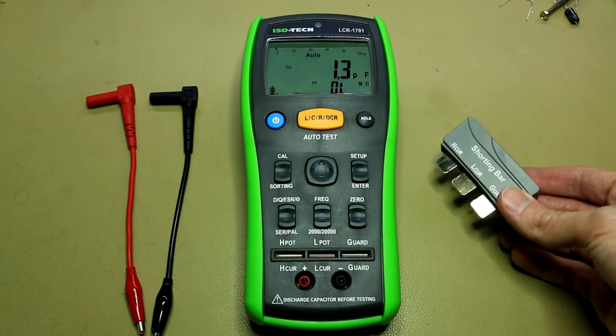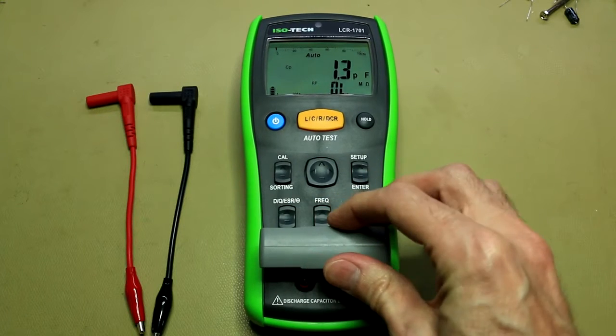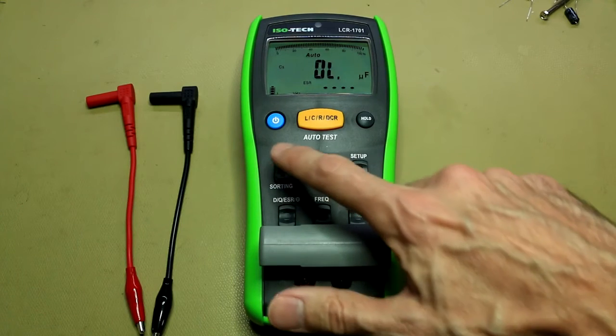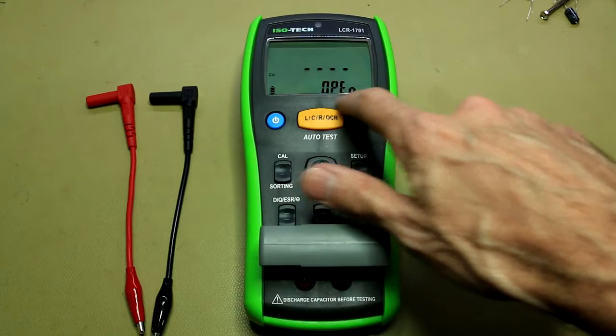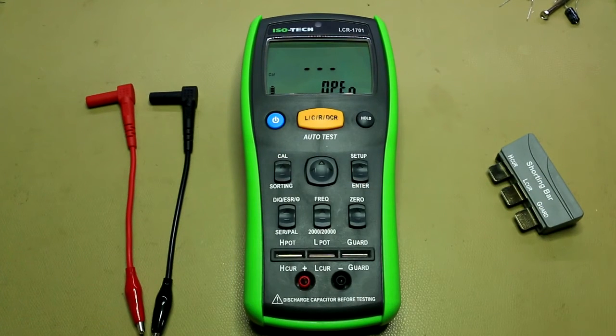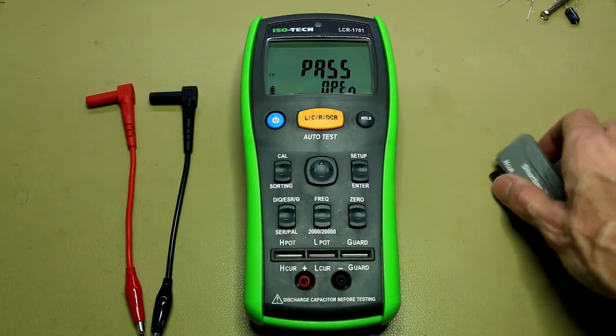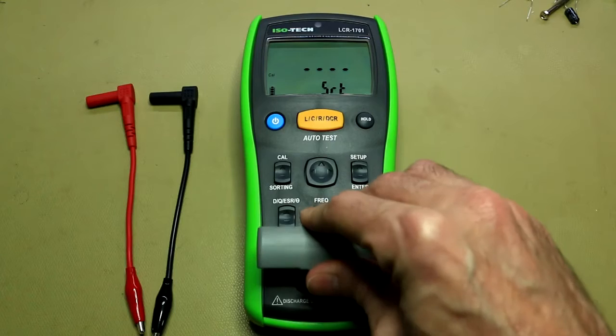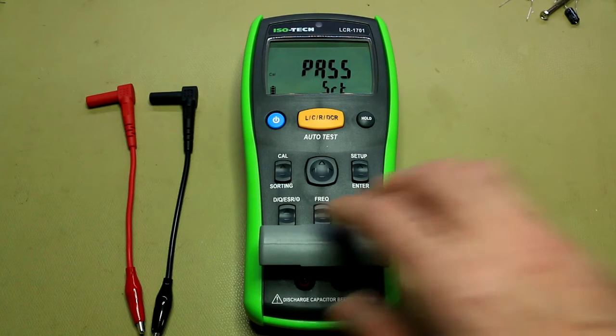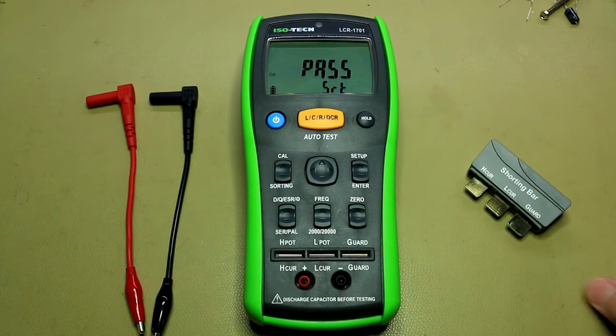Right, so to calibrate the unit, basically take the shorting bar, plug it into the probes there, or where you would normally put the components, and click calibrate. First it asks you to do an open calibration. So yes, I'll just remove the shorting bar, press the calibration button, it runs through the calibration. Okay, and once it says pass, you press calibrate again. Then it says short, that's when you put the shorting bar in. Then press calibrate again. There we go, passed, and we can remove the shorting bar. Press calibrate. Right, then it defaults to this automatic mode.